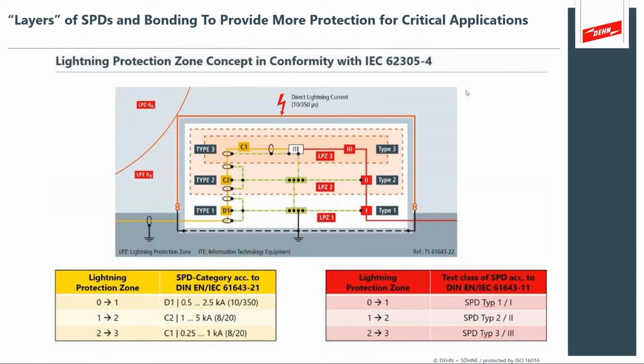I think that provides some background to that. Yes, I'd just also like to mention that as you move closer to the terminal equipment with a coordinated system from a Type 1, a Type 2, and a Type 3, like Mark illustrates in the slide, you also have smaller voltage protection levels, meaning that the amount of voltage that the equipment is now exposed to just keeps on getting smaller and smaller. So you have this progressive protection scheme addressing even more sensitive equipment.